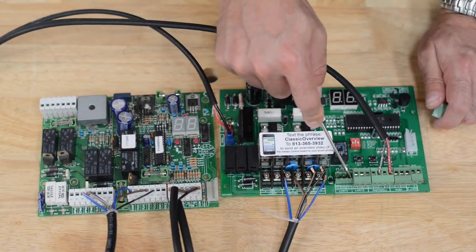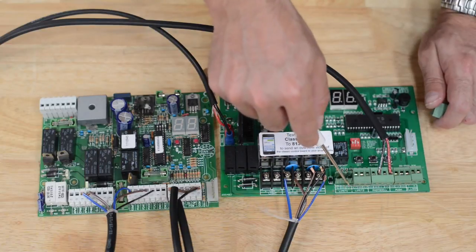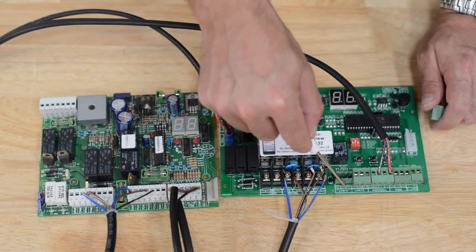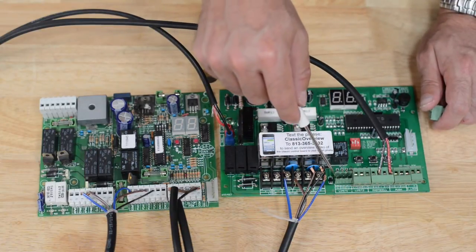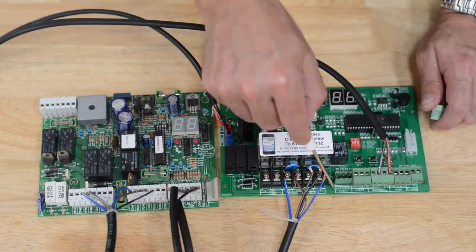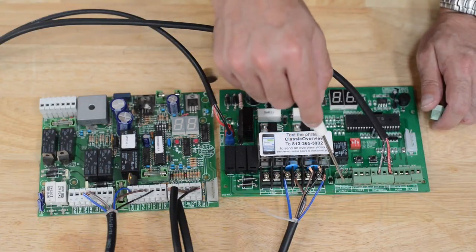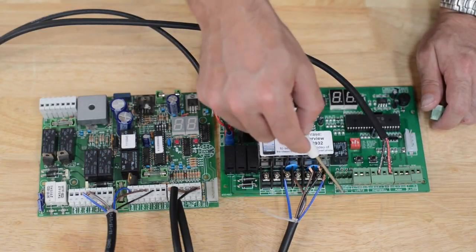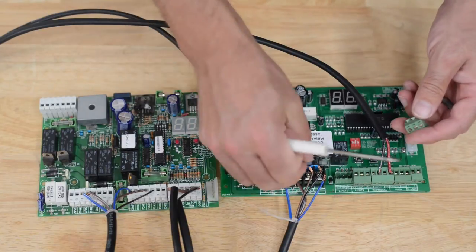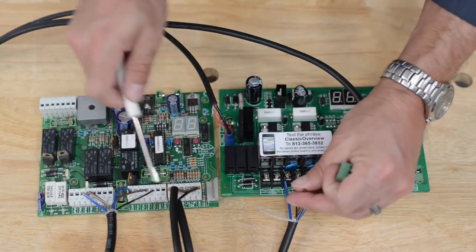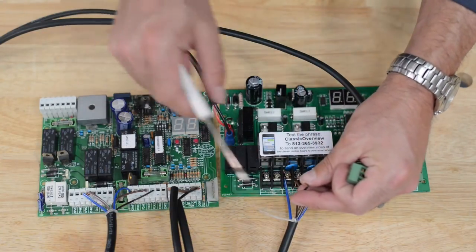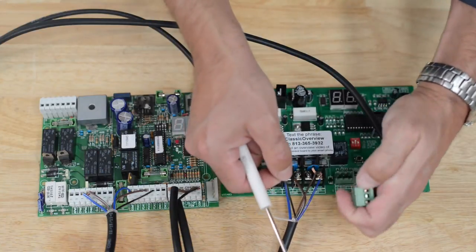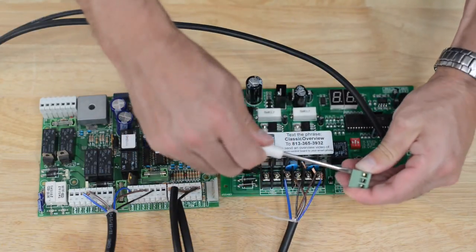On this block, the closed limit is the third switch. You see it says CL1, closed one. And then the first one is OL1 for open one. Again the center is COM. So we're going to put the black one, because that was in your FCA, the third terminal over, into the first terminal on this side.